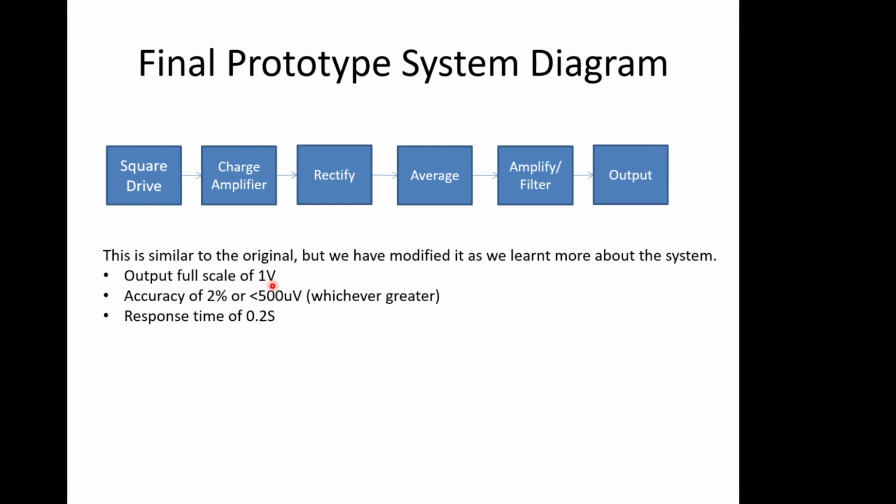Our output we've tested. We've got a full scale of 1 volt because we scaled it properly, and we've tested the accuracy, and we're inside the accuracy, and we're inside the response time as well. So that's sort of an approach to how you might design these kinds of systems.